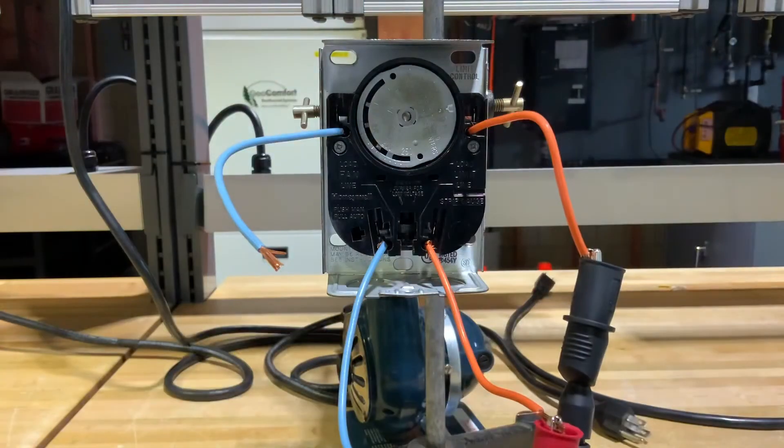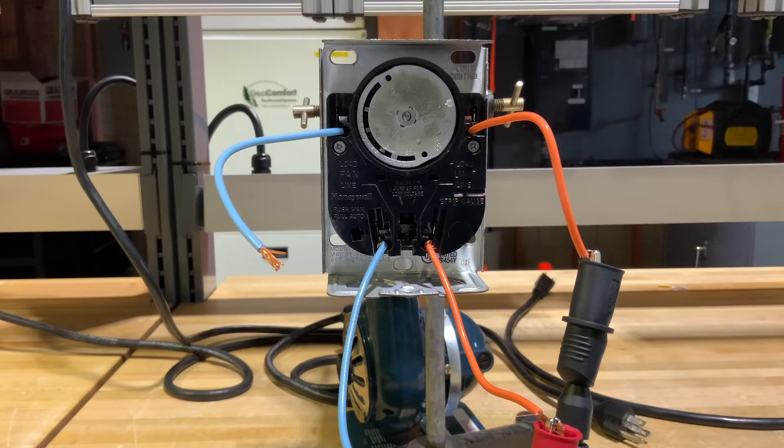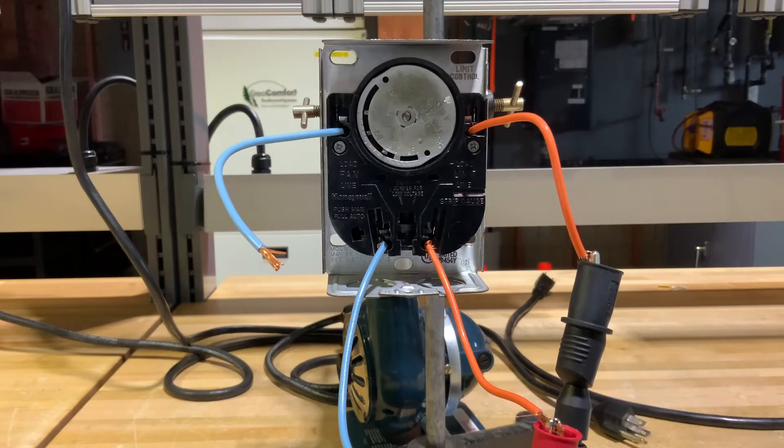When I hit a certain temperature - whatever that's set for, that looks like about 180 - so when I get under 180 degrees, that limit should reset, send power to our primary controller and try to start the unit again.